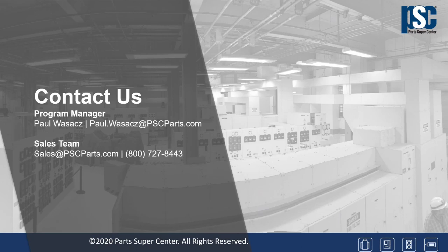So the reason we know that is because during design testing, we had that actually happen. So there were several iterations of the design before we found a mixture of epoxies that worked correctly. So all of the service advisories that we've talked about, including the primary disconnects, have been completely design tested by General Electric at high power labs when necessary, and they all meet the requirements of IEEE C37.59, which talks about modifications and substitutions of major components and parts within the switchgear and circuit breakers. So for those reasons, we do not recommend repotting them.